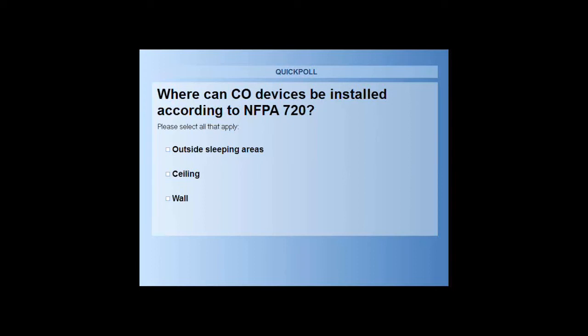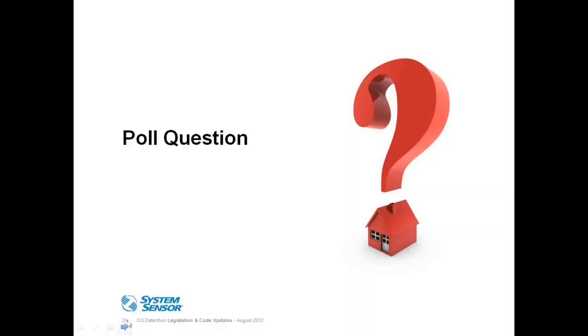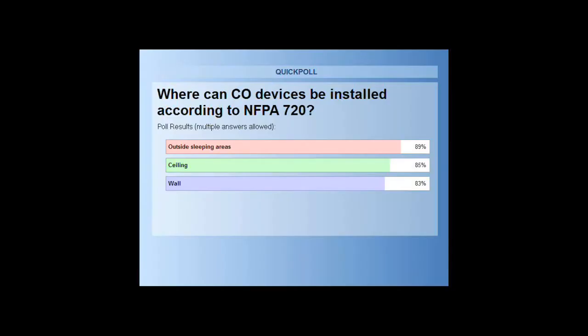Good question. If you look at the CO1224T and TR, and I think most other manufacturers as well, it operates almost like a 4-wire smoke detector. In other words, you have an initiating device circuit and then you have a separate power circuit. So you connect that power circuit to the control unit, and whatever the auxiliary power output of that control panel is, that would determine how many of these CO detectors you could install on a control unit.